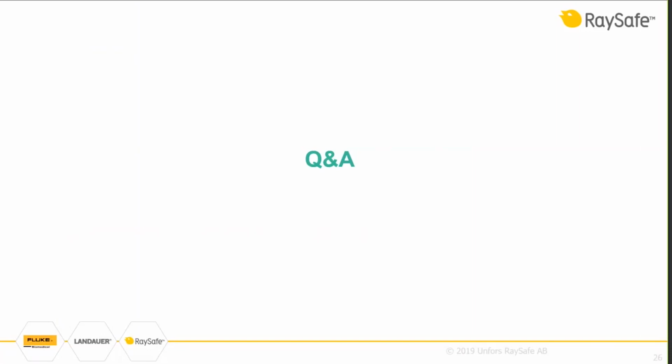All right. Many questions here. We just take the next one. Can the 452 measure pulsed radiation? Yes, it measures pulsed radiation quite well, and it covers everything from the single pulsed X-ray machines in the hospitals to linear accelerators that have a very high frequency pulsed radiation. Great.